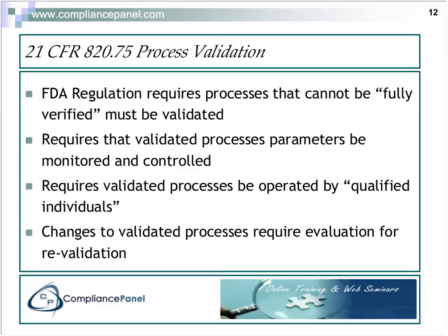It does require that validated processes be operated by qualified individuals, and what this means is it's more than just the basic training of some operators on the floor, but rather there must be some specific training that relates to these validated processes so that we can demonstrate that the people that are operating these processes know what they're doing and know or are able to recognize when something is going out of specification and what to do about that. So this qualification requirement is a little bit more stringent than the normal training requirement for a production operator.